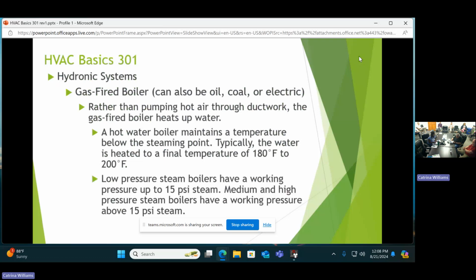If you get into steam, there's various things for pressures you have to work with. A low pressure boiler has a working pressure up to 15 pounds. You get above that, over 15 pounds, those are medium or high pressure, and those get pretty special. Get up to a certain point, you have to have a licensed operator on site at all times to operate, where low pressure boilers aren't quite as critical. But what does that give us between the two?